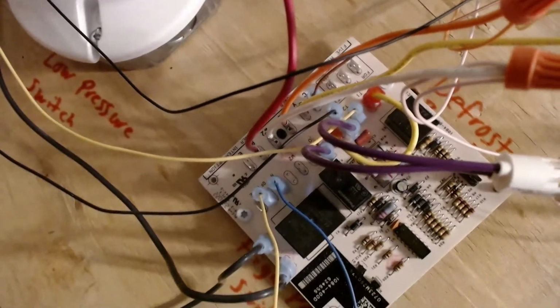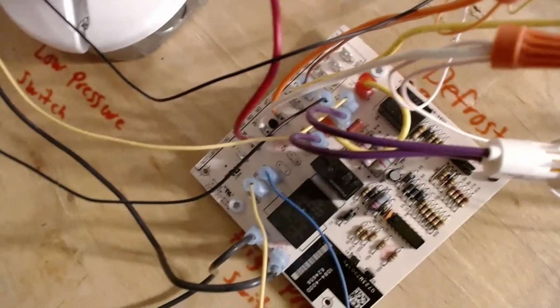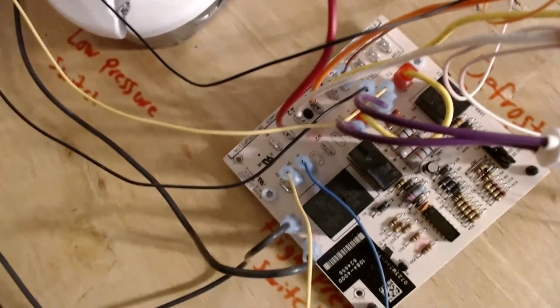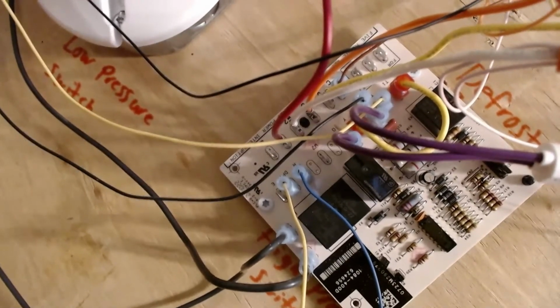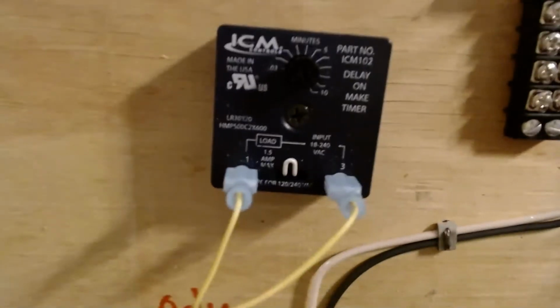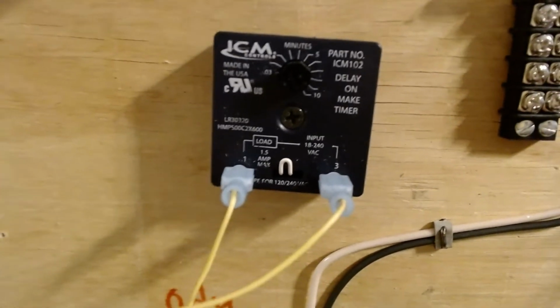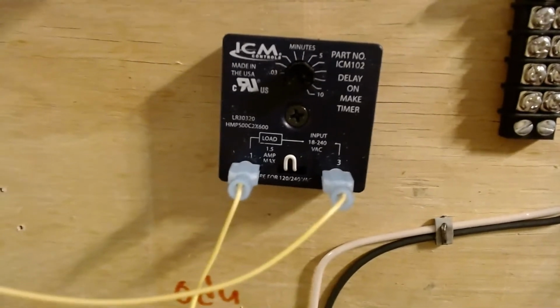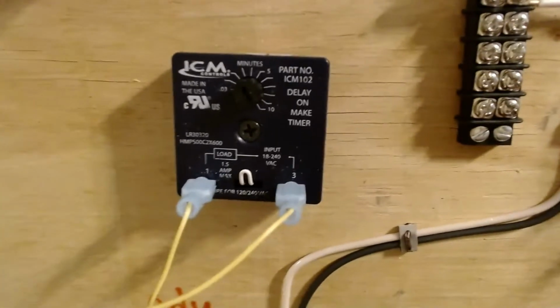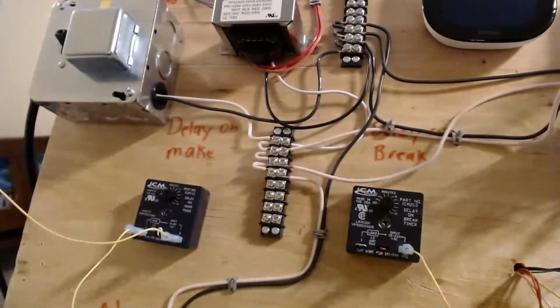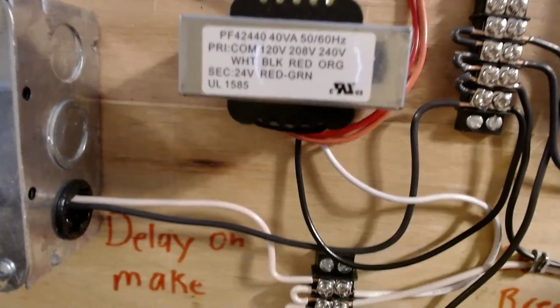Defrost board. Wires galore for people to have OCD problems. And we'll go over here to our delay on make. As you can see, same timing settings. Cut from 120 to 240. All right. Our little terminal strips that center power everywhere.